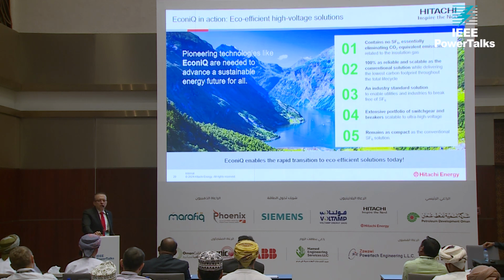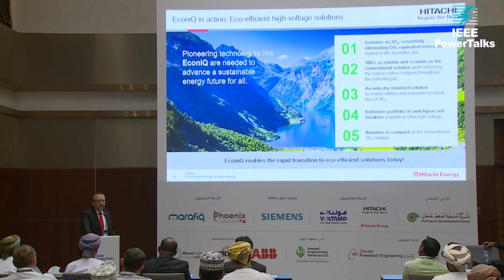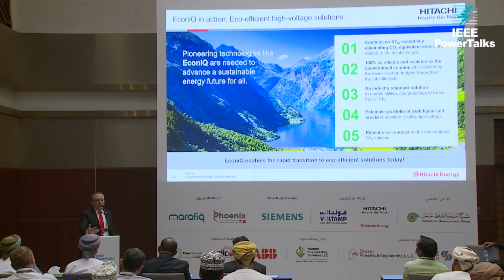If we compare a GIS substation to an AIS substation at the same 400 kV level - say with 15 bays of 400 kV GIS - the equivalent AIS substation might need, for example, 10 times more space, and maybe 5 times more concrete and other materials. This is why we use SF6, to have a compact solution.